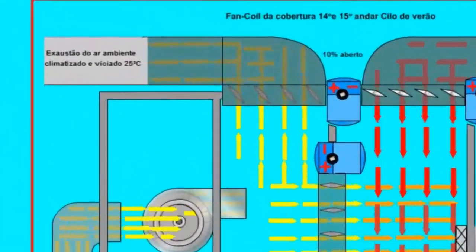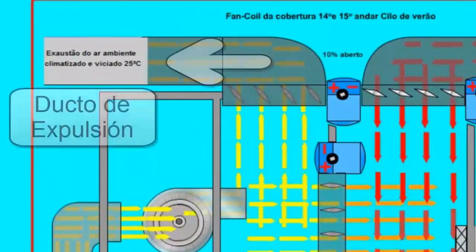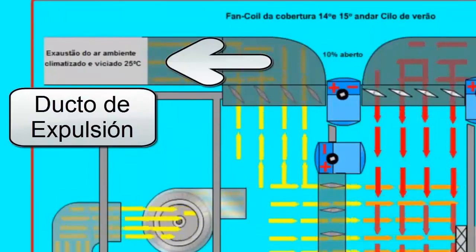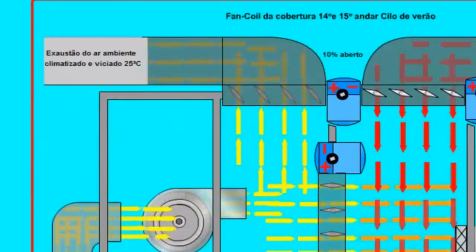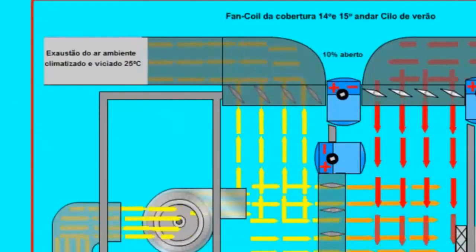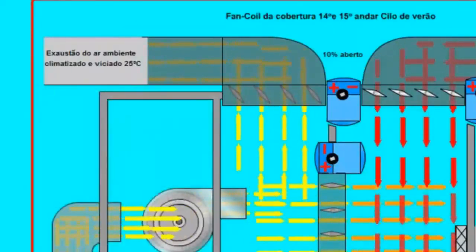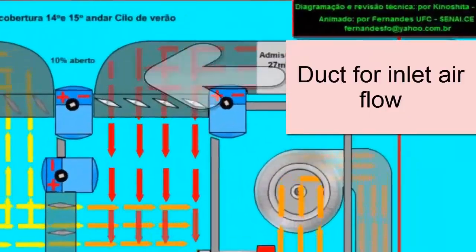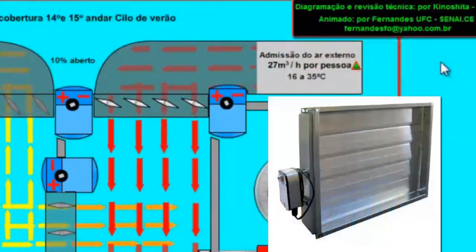Air conditioning exhaust duct. Through this duct, a percentage of the already conditioned air that comes from the premises is expelled to maintain the CO2 concentration values at the recommended PPM. To control the amount of air being expelled, there is a damper which is currently open at 10%. To replace the flow that has been expelled, there is an inlet duct from the outside, responsible for bringing fresh air from the street. The air flow is controlled by means of a grill, which in this case is open at 10%.